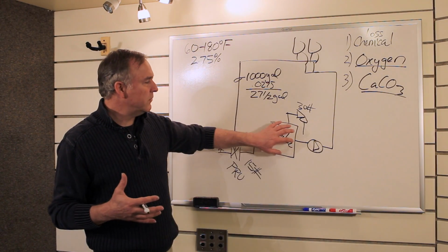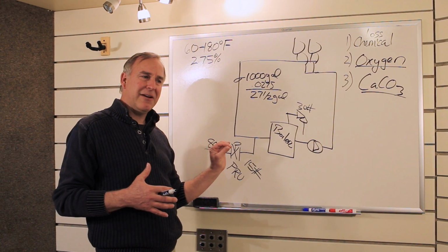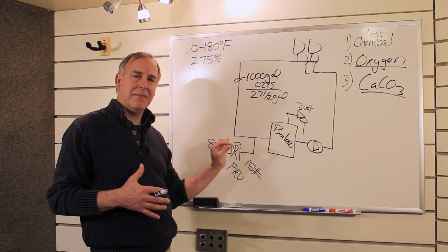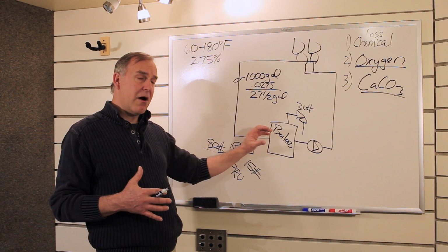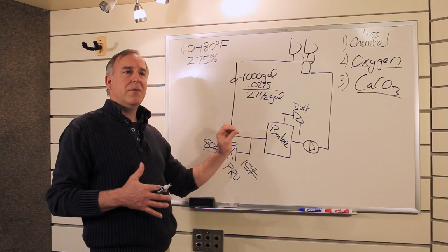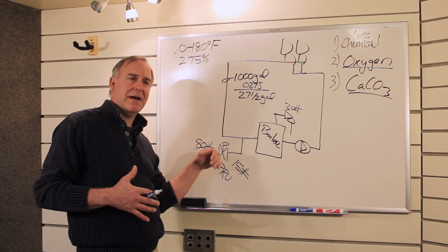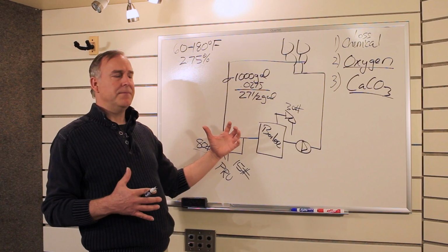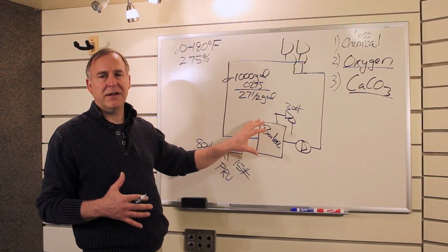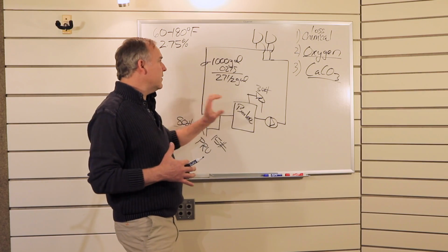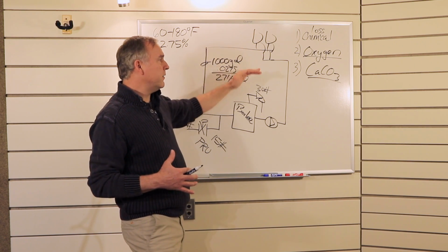And it likes to plate out in the worst possible place, which is the boiler. So the sections in there will end up getting a layer of lime and scale that builds up over time. And that insulates those heat transfer surfaces, making them less efficient. But also you end up in a scenario where that heat transfer metal in the boiler has to get hotter and hotter to drive the heat through there. That puts a lot of stress on it. In a cast iron style boiler, we often would see sections that would crack and fail as a result of all that lime and scale. So, very important that we keep that fresh water out of our hydronic system for all those 3 reasons.